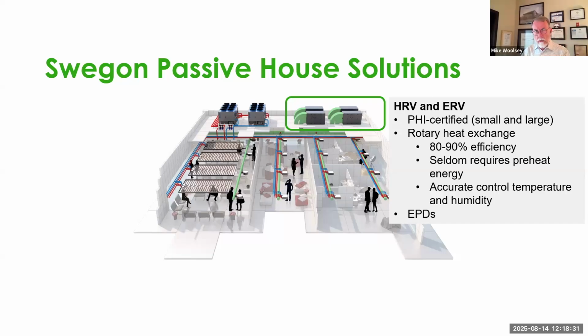That can save quite a bit of energy for those few hours a year when it's dramatically cold outside. The other thing we do with the rotary heat exchanger that you can't do with a plate is adjust the speed of rotation to control temperature and humidity. That allows us to use the rotor as the first stage of heating and cooling — it's very accurate, and it really changes the way we think about heating and cooling. We get so much heating and cooling control out of the ERV that supplemental heating and cooling is really limited to the coldest or hottest days of the year.